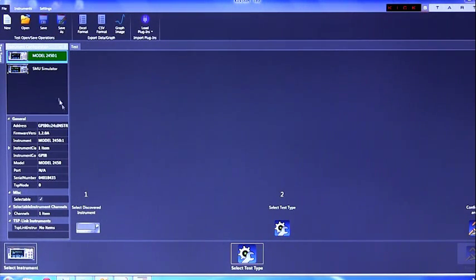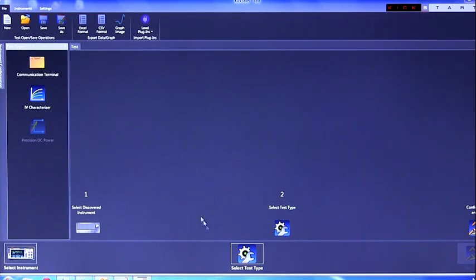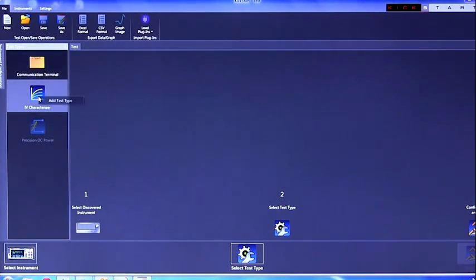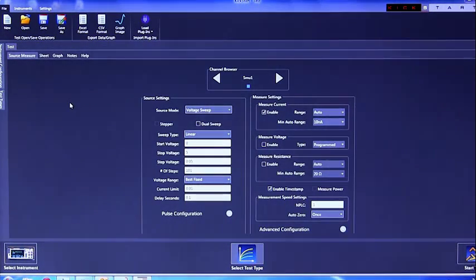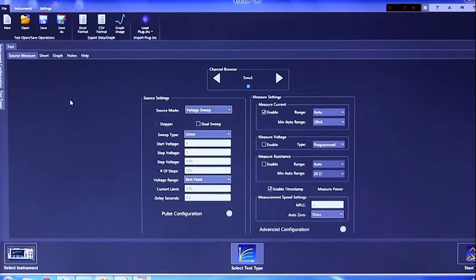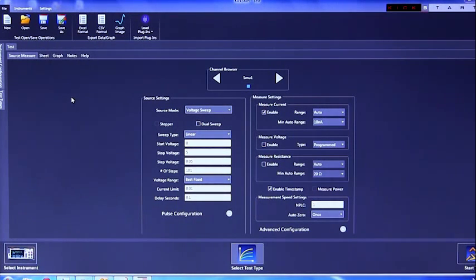You will then want to select your test type. You can do this by navigating over to your test type, right clicking on it and selecting add test type. This test will do a basic voltage sweep ranging from 0 volts to 5 volts in 101 step increments.